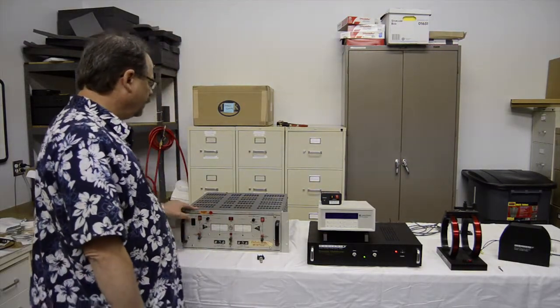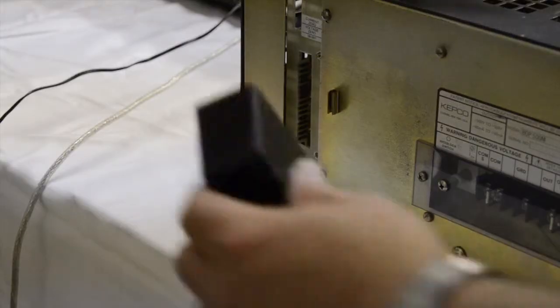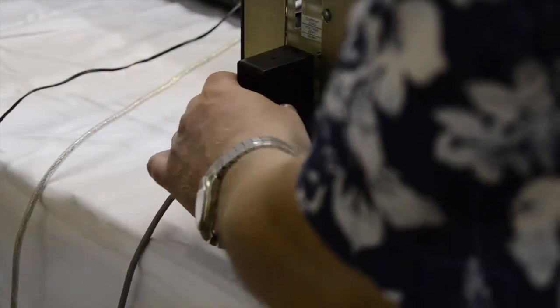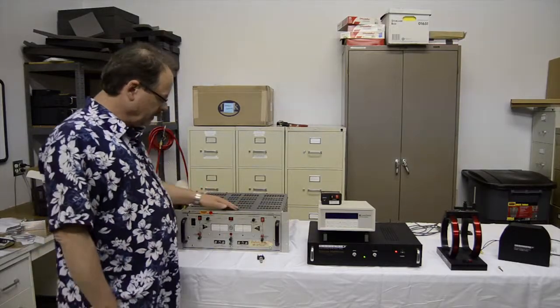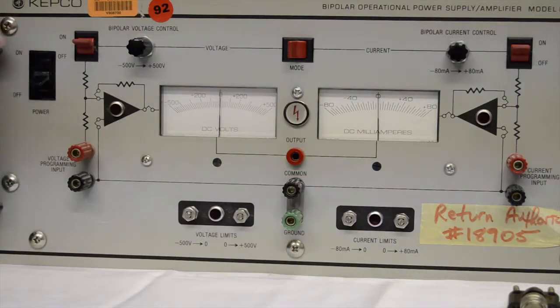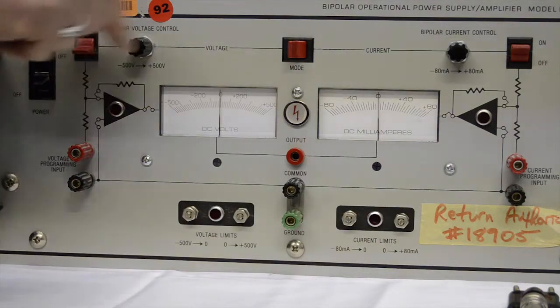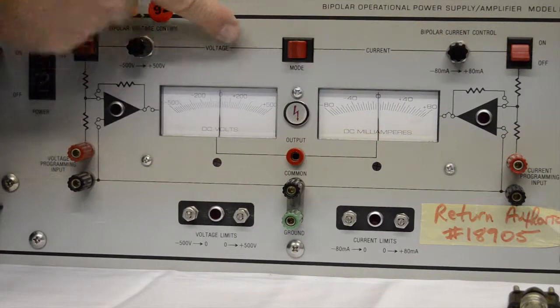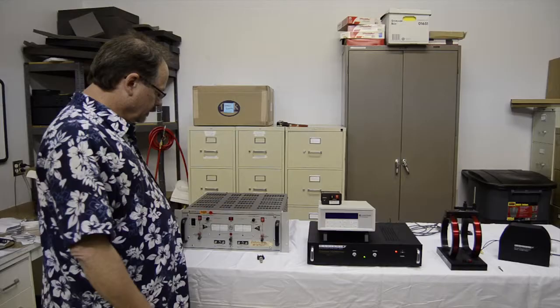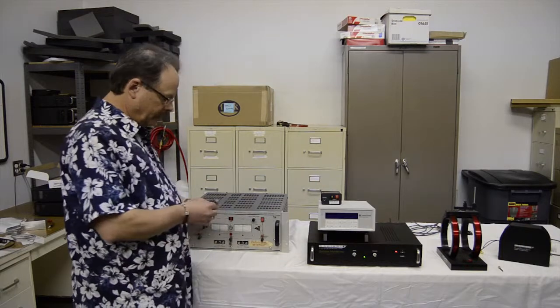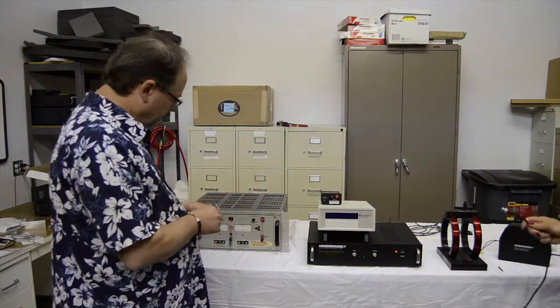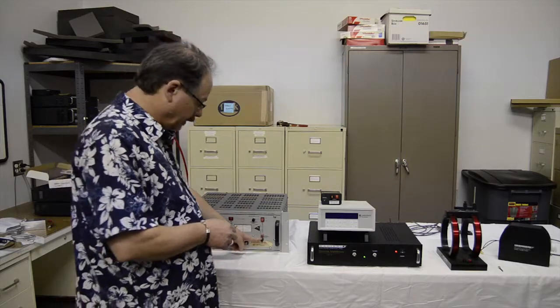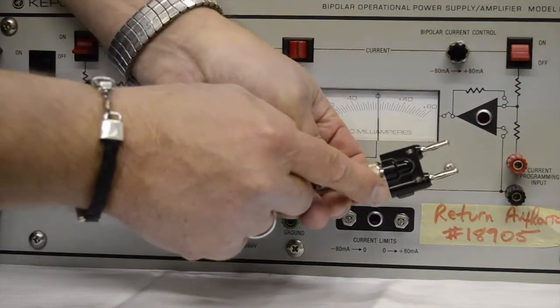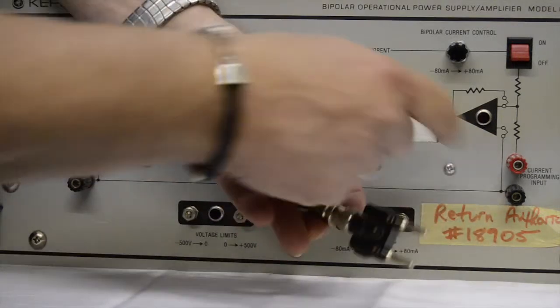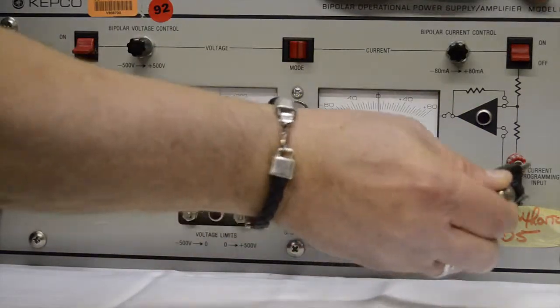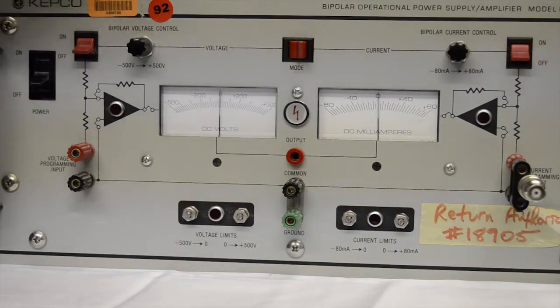In order to set this up, we're going to first ensure that the PC15 connector is attached to the rear panel of the current amplifier. Then we're going to set the voltage switch off. We're going to set the current switch off. We're going to put the mode switch into the current position. Then I'm going to connect a BNC to banana adapter into the current programming input of the amplifier. The adapter has to go ground plug to ground, so that the tabbed portion of the connector goes to the black connector at the amplifier.